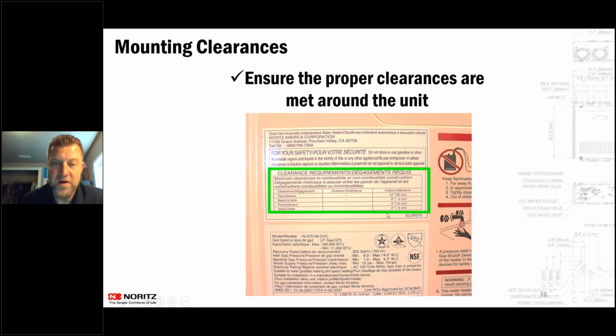A lot of ours now, the code is you need to have at least 24 inches in front of the unit to be able to take the door off to actually work on it if you needed to, and then 18 inches to the sides. And that 18 inches to the side is just because the data plate and everything is on the side of the unit, and you need an area where you can actually stick your head in there to see what the data plate is.